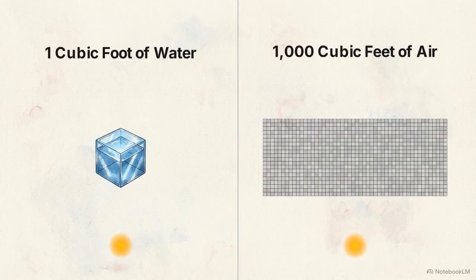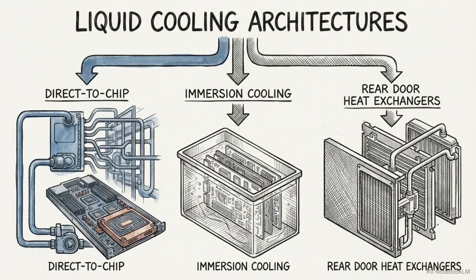This table compares the raw thermodynamic properties of air and water. Look at the top row. Water conducts heat approximately 24 times better than air. Moving down to the density row, water is about 1,000 times denser. In practical terms, a single cubic foot of water can remove the exact same amount of thermal energy that would require a massive 1,000 cubic feet of air. To leverage this physics advantage, the industry relies on three distinct architectural paths.